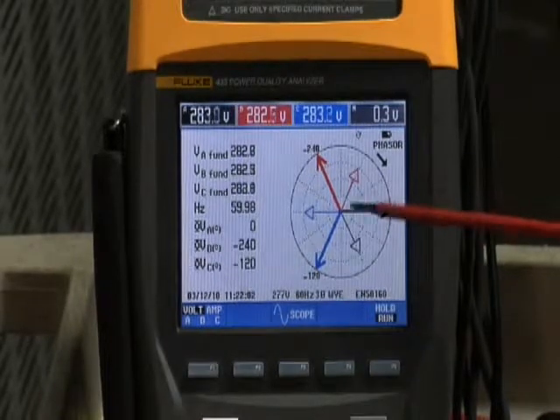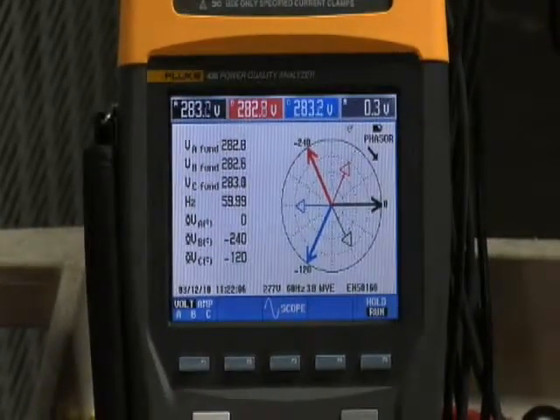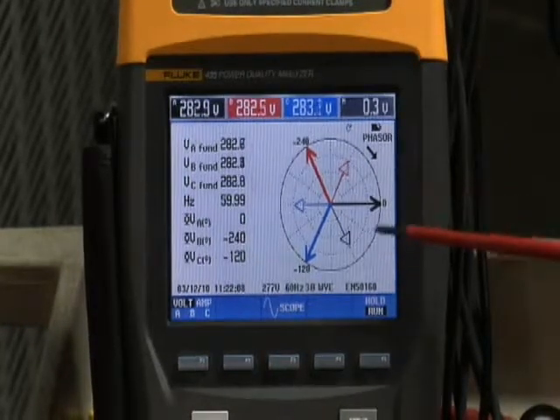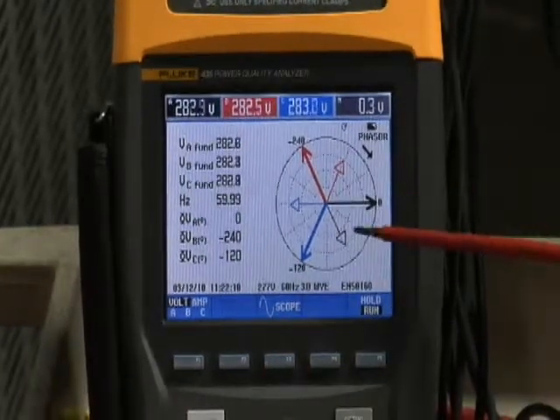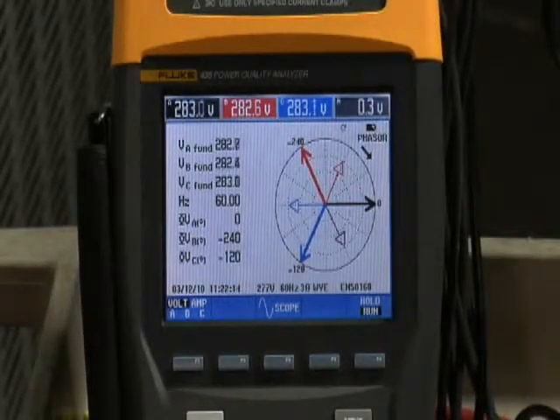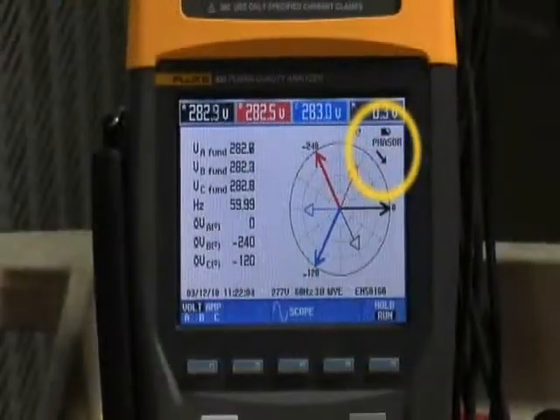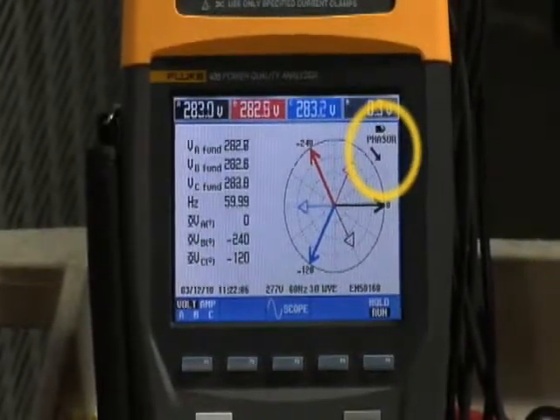When we go back to the phasor diagram, we find some displacement between phase A voltage and the phase A current. However, we notice that the phasor arrow is in the wrong direction — it should be pointing counterclockwise, but it's showing a clockwise direction.